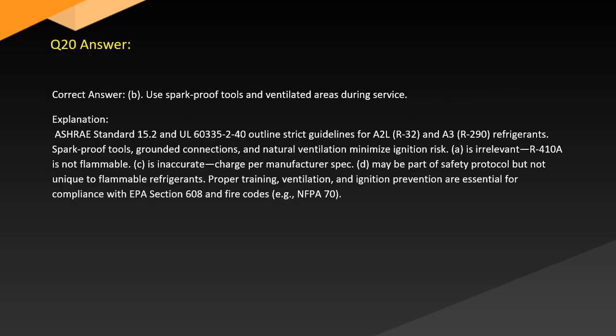Answer. Correct answer: B. Use spark-proof tools and ventilated areas during service. Explanation. ASHRAE Standard 15.2 and IEC 60335-2-40 outline strict guidelines for R32 and R290 refrigerants. Spark-proof tools, grounded connections, and natural ventilation minimize ignition risk. A is irrelevant. R-410A is not flammable. C is inaccurate. Charge per manufacturer spec. D may be part of safety protocol but not unique to flammable refrigerants. Proper training, ventilation, and ignition prevention are essential for compliance with EPA Section 608 and fire codes, e.g., NFPA 70.